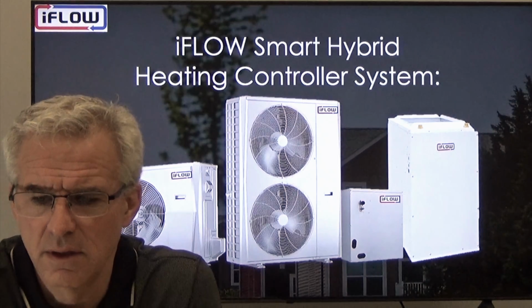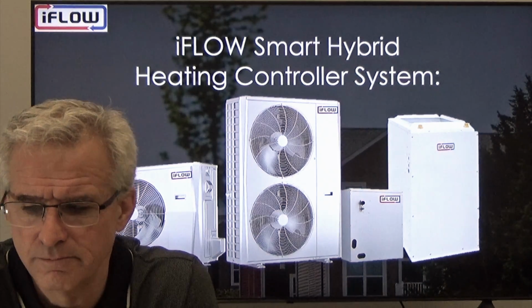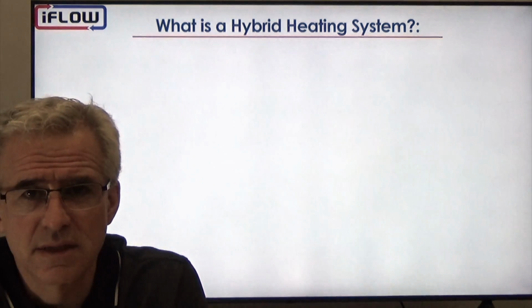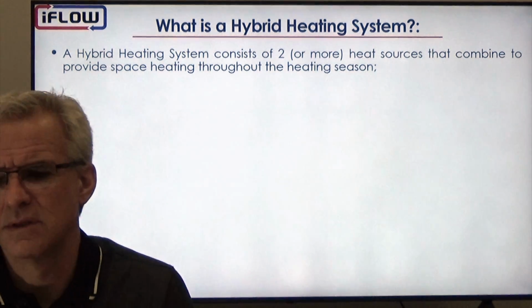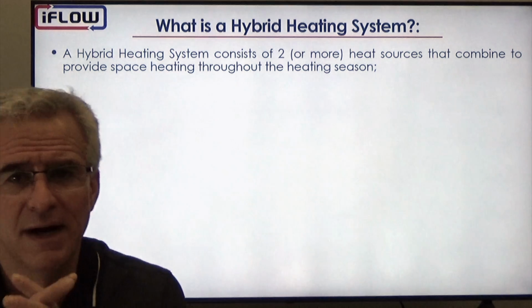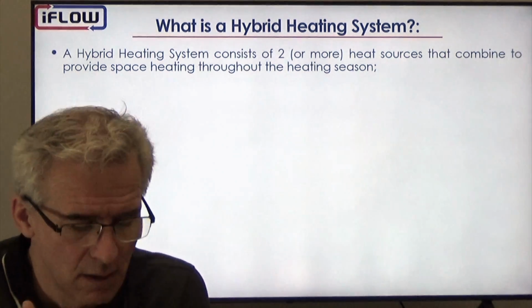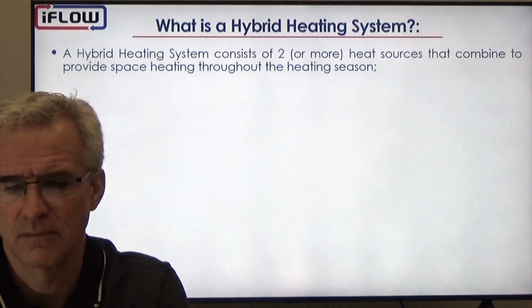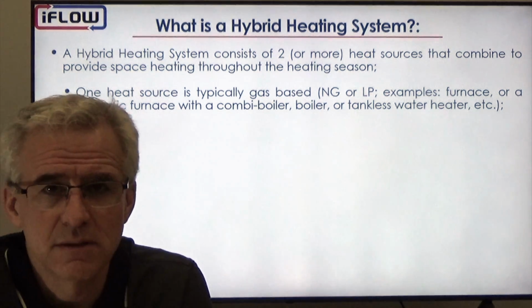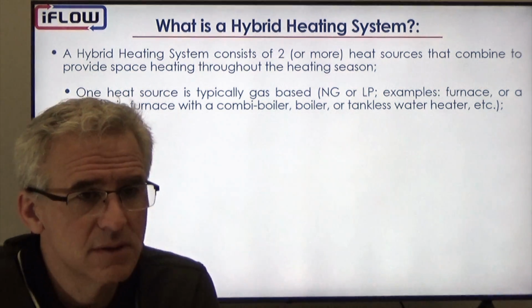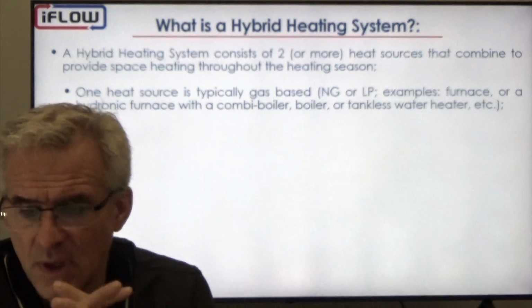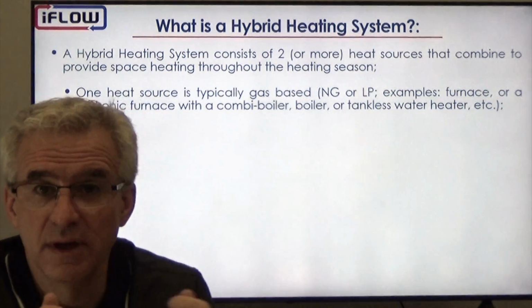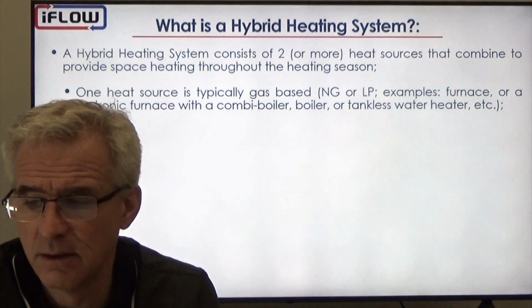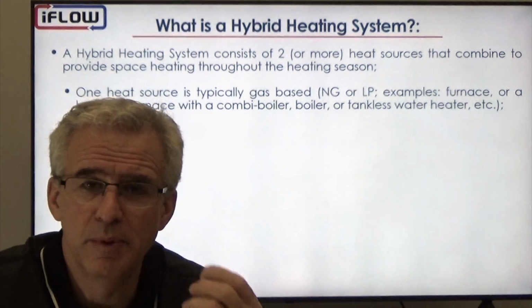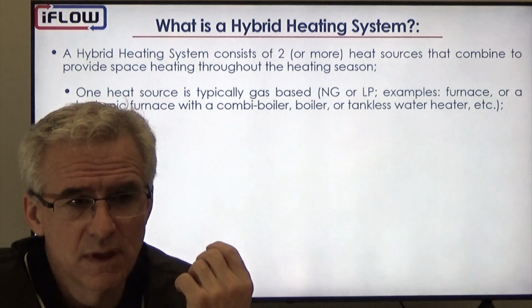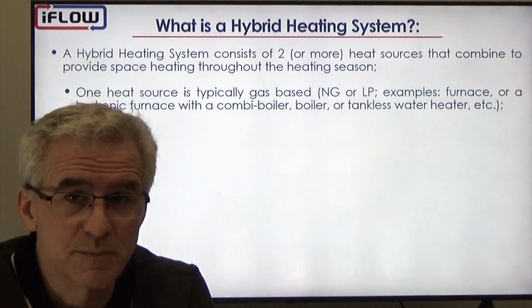In this segment, I'd like to look at our iFLOW Smart Hybrid Heating Controller. So what is a hybrid heating system? A hybrid heating system consists of two or more heat sources that combine together to provide the heating throughout the heating season. One is typically gas-based, so it could be a gas furnace, it could be a combi boiler with an air handler, or a boiler with an air handler. It could be a tankless water heater with an air handler. But the heating appliance would be gas-based.